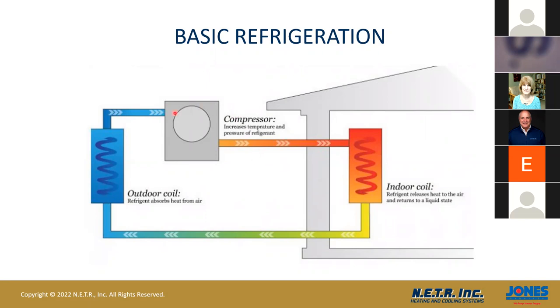So basically it's a reverse cycle from an air conditioner, where in the summertime you have cold air coming out of here. In the wintertime, you have warm air coming out of here. There is a valve inside the unit that switches this over from heating to cooling and back. So when you do purchase an air source heat pump, you get cooling as well. So we look at this from an air conditioning and heating side.